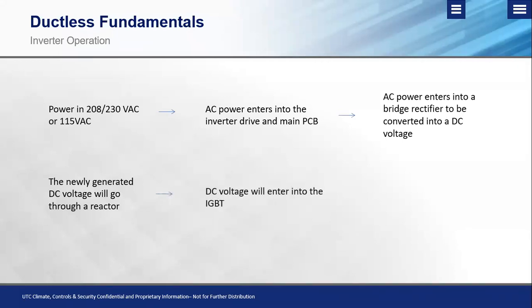Okay, so once we've taken that AC power, rectified it over into DC voltage, and run that DC voltage through our reactor or inductor to clean it up, we're now going to enter into the IGBT, which stands for insulated gate bipolar transistor switch. It's essentially a fancy name for a switch that pulses DC voltage to three common terminals. Those three common terminals are listed as U, V, and W. And the really nice part about those three common terminals is that they are used across the board, whether you're dealing with a Mitsubishi system, a Daikin system, or a Carrier ductless system.